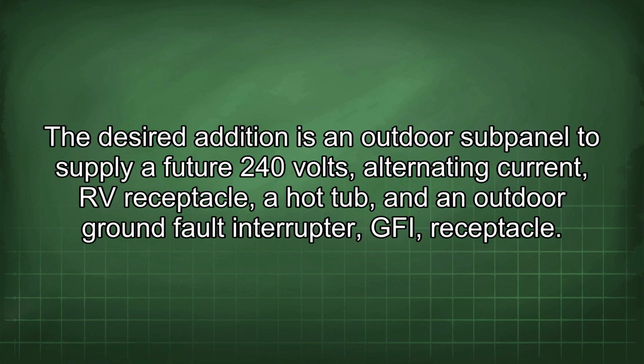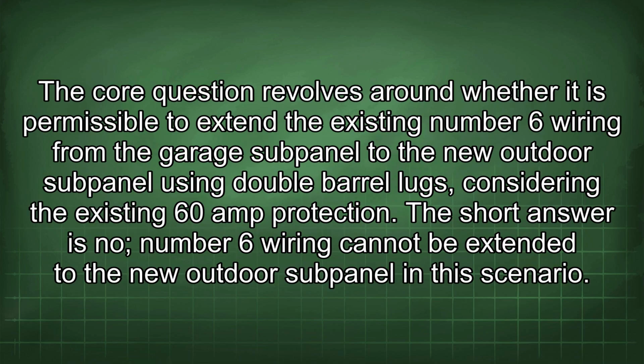The desired addition is an outdoor subpanel to supply a future 240 volts alternating current RV receptacle, a hot tub, and an outdoor ground fault interrupter (GFI) receptacle. The core question revolves around whether it is permissible to extend the existing number 6 wiring from the garage subpanel to the new outdoor subpanel using double barrel lugs, considering the existing 60-amp protection. The short answer is no. Number 6 wiring cannot be extended to the new outdoor subpanel in this scenario.